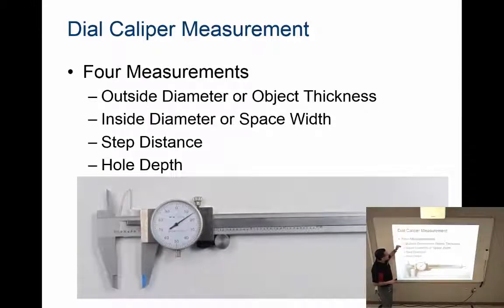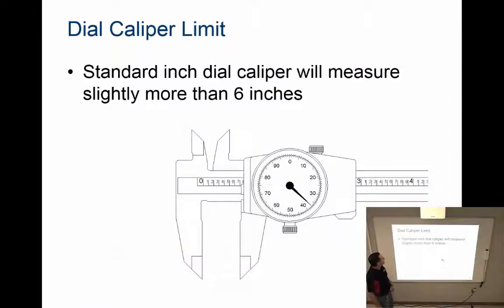We're talking about outside diameter, inside diameter, step distance, or hole depth. Again, no matter which way, we're going to read the instrument the same way. There are some limitations, the upper limit being six inches, so anything over six inches we probably won't measure with this tool.